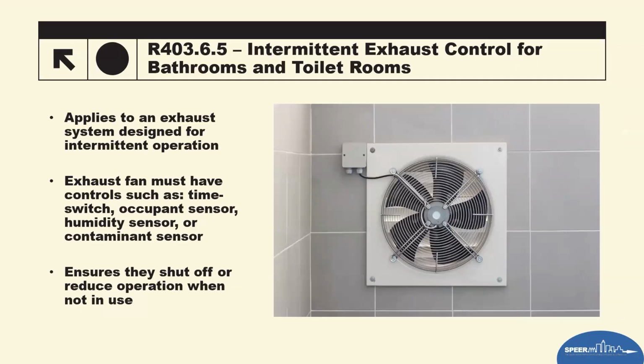And then, of course, intermittent exhaust controls for bath fan and toilet areas. This is something new as a requirement. So if the systems are designed to operate intermittently, which most bath fans are, rather than continuously, the code mandates that they must include automatic controls such as time switch, occupant sensors, humidity sensors, contaminant sensors. I'll mention this again: this is what's in the book. This is not what's been adopted by SECO. This is what's in the book.